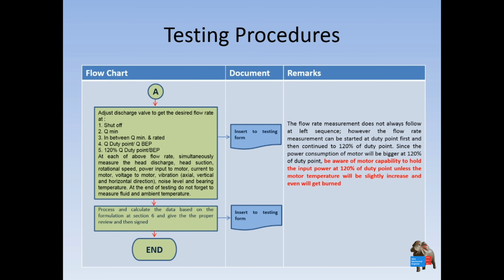Before testing, of course, you have a data sheet of the pump. So for this next step, you should prepare it before testing the pump. You have to decide how many points of testing you want to perform. Based on the ISO standard, you have to test at least 5 points. The first point is the shut-off point, where the discharge valve is fully closed. The suction must of course be fully open, and we call it the shut-off situation, and run the pump.